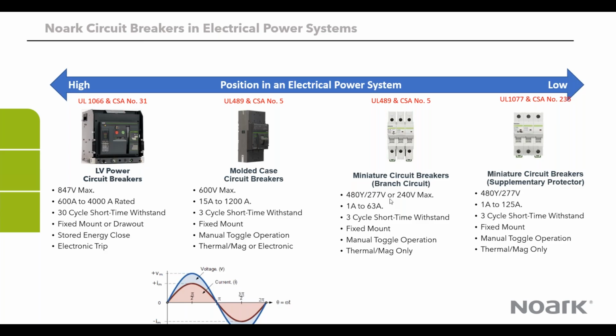And then we have the miniature circuit breakers, which are the smaller circuit breakers, mostly used in the branch circuit. And then the fourth one is the supplementary protectors, which are used as a backup protection. So you cannot use the supplementary protectors as a standalone device. You have to have a branch circuit protection, a UL 489 breaker, upstream. And so where you find the application of a supplementary protector is mostly in control circuits, industrial control circuits, maybe you're trying to protect a control transformer, for example. So those are the applications where you find those types of miniature circuit breakers, the supplementary protectors.